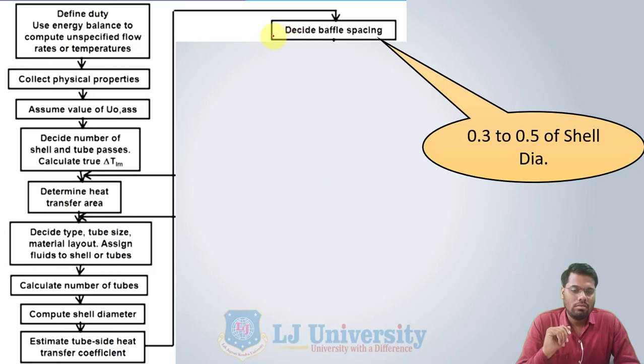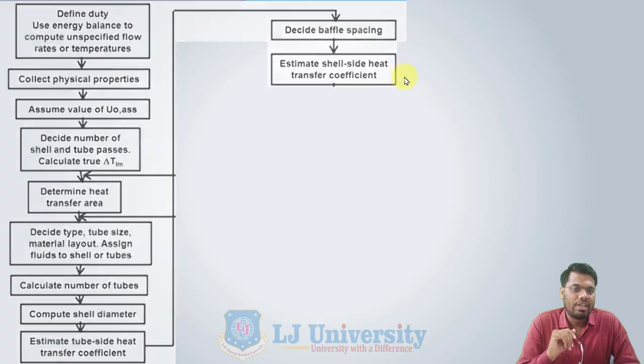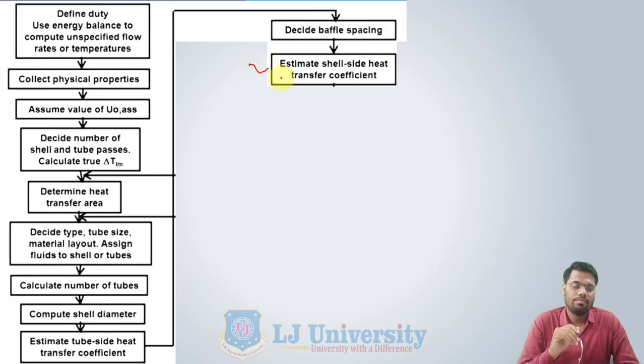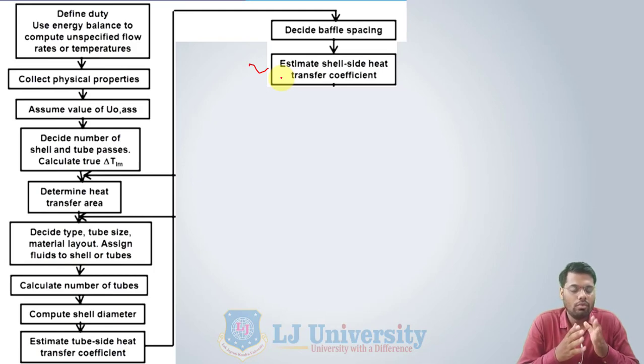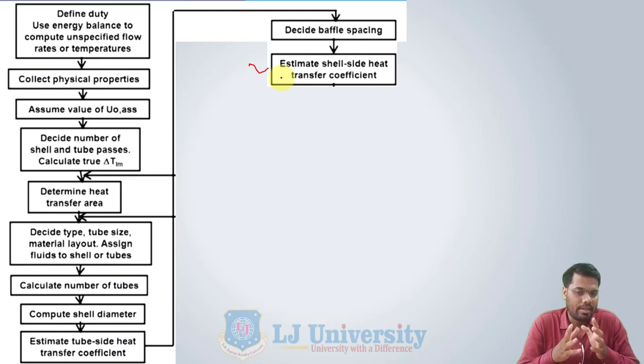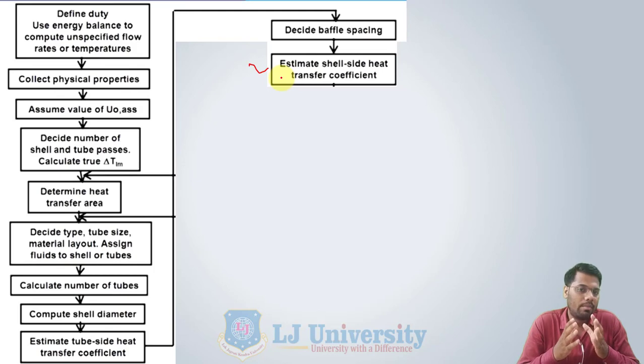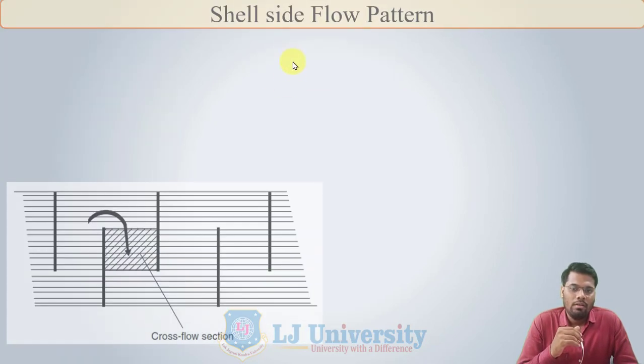We have already decided the baffle spacing, which is generally between 0.3 to 0.5 of the shell diameter. After that, we have to estimate the shell side heat transfer coefficient. The shell side heat transfer coefficient is very difficult to calculate. We have two methods: one is Kern's method and the second is the Bell-Delaware method. First, we will discuss the basic method, which is Kern's method, and in upcoming videos, we will discuss the Bell-Delaware method.